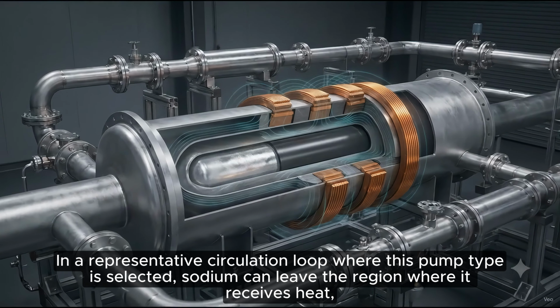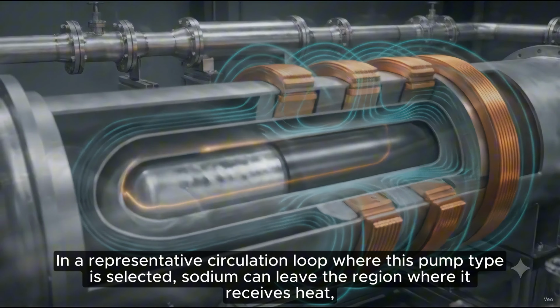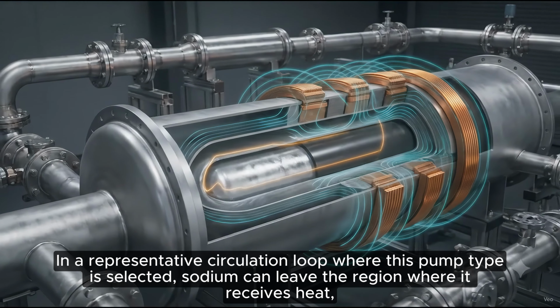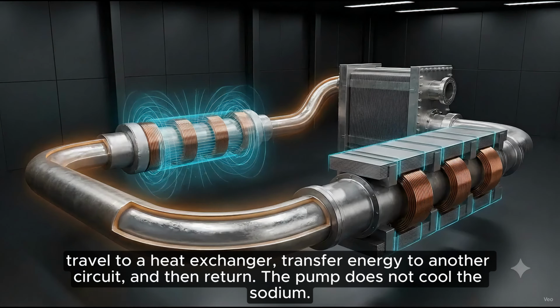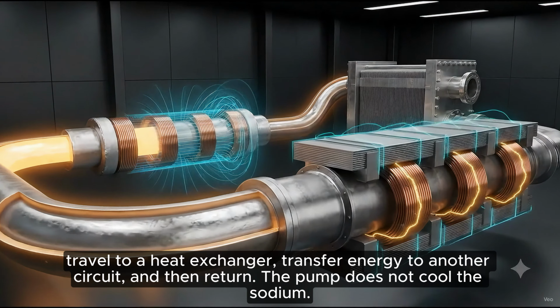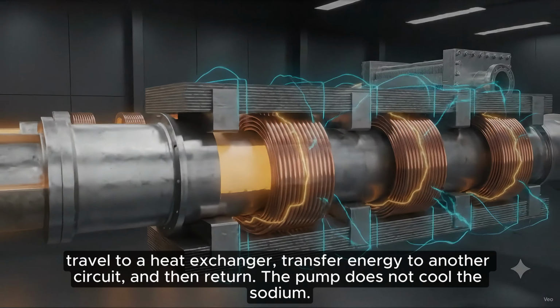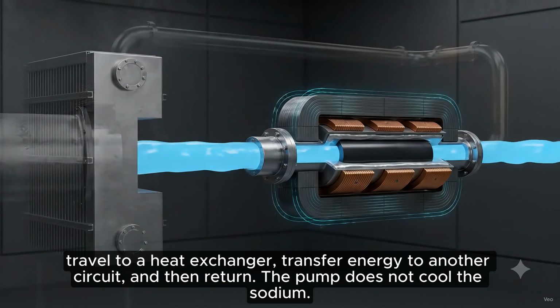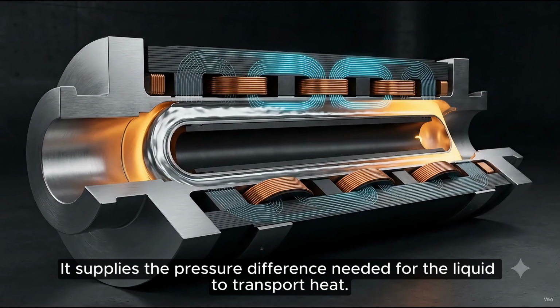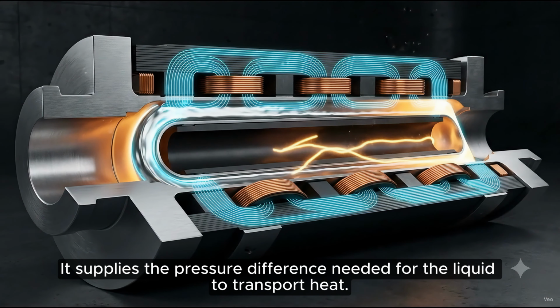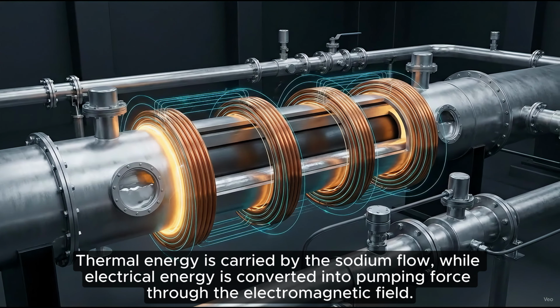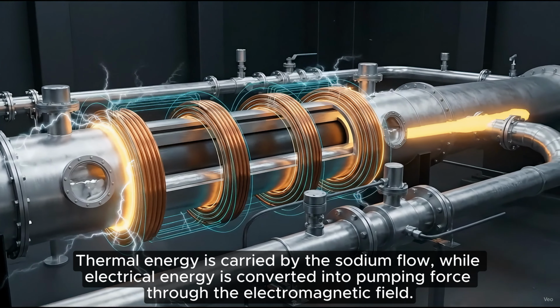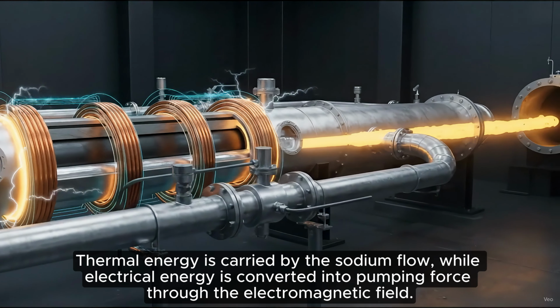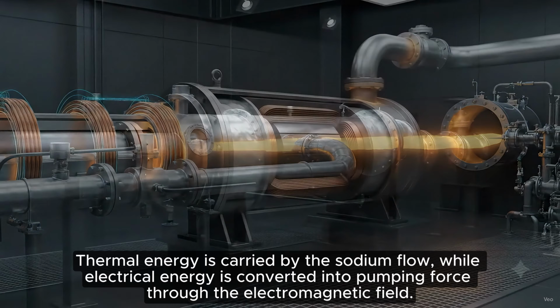In a representative circulation loop where this pump type is selected, sodium can leave the region where it receives heat, travel to a heat exchanger, transfer energy to another circuit, and then return. The pump does not cool the sodium. It supplies the pressure difference needed for the liquid to transport heat. Thermal energy is carried by the sodium flow, while electrical energy is converted into pumping force through the electromagnetic field.